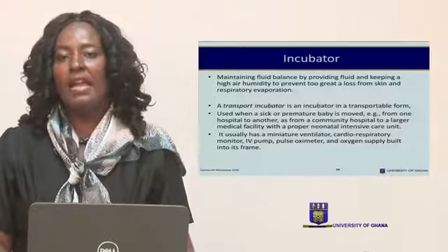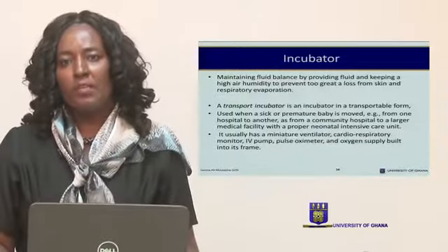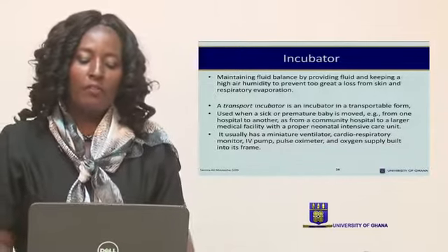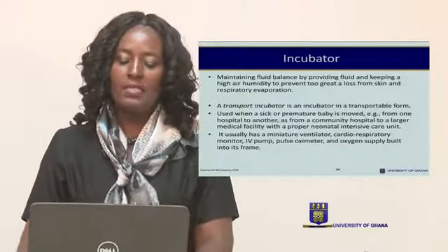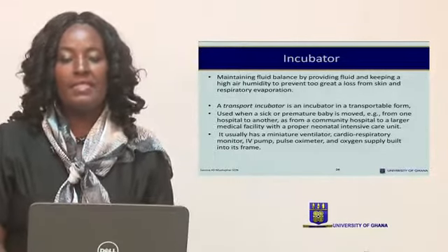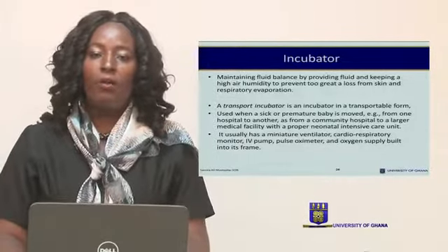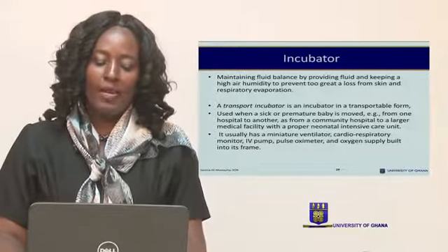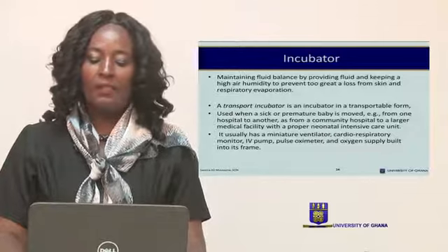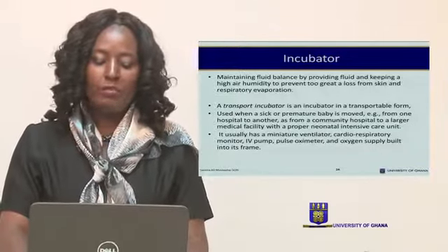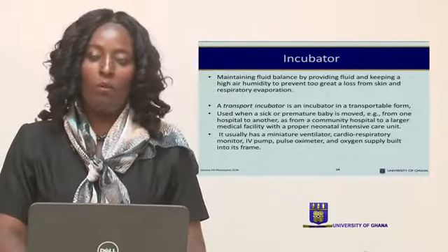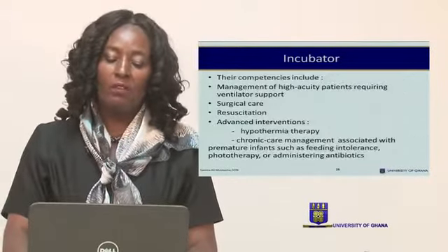We have also said earlier, and you have seen the transport form of incubator. So in cases where we have to transport the newborn from one institution or community to a larger health facility, the incubator also helps us to do that. And it also has outlets, as I said earlier, that we are able to pass through to administer care in the form of IV pump or pulse oximetry or even giving of oxygen.